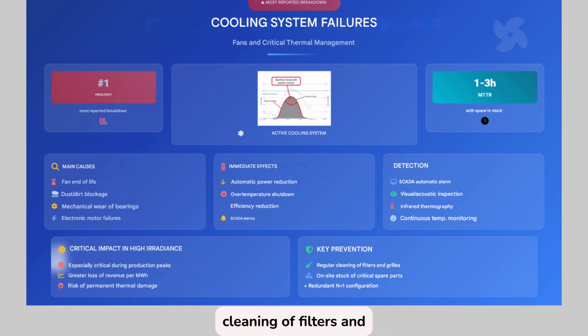Regular cleaning of filters and grills, availability of spare parts on site, and if possible, incorporating cooling redundancy through an N+1 configuration. Planning monthly inspections with thermography and SCADA data can make the difference between a stable plant and one that steadily loses performance without anyone noticing. In short, this isn't the most expensive failure, but it is the most repetitive. And as is often the case in industrial operations, invisible and cumulative costs are those that most affect the bottom line. Therefore, thermal management must cease to be a secondary issue and become a priority in any well-structured O&M strategy.